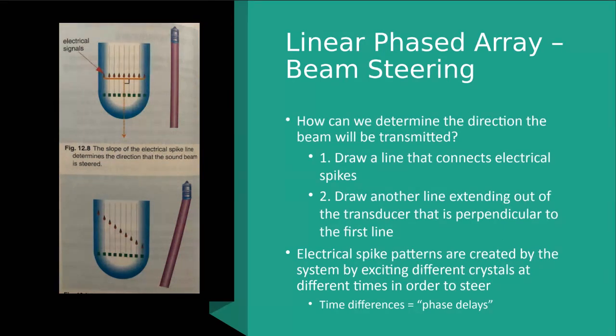Now we had 100 to 300 elements excited and activated in our transducer. When that happened, they created 300 little smaller waves. All of those smaller waves got excited. They joined together, they unified, and they said, okay, we're going to travel as one. Think of a flock of birds. You have the whole flock, and they're all heading in the same direction, but each individual bird's kind of doing their own thing. That's a better way to talk about steering and how these different elements join together.